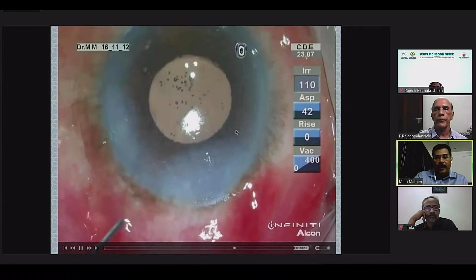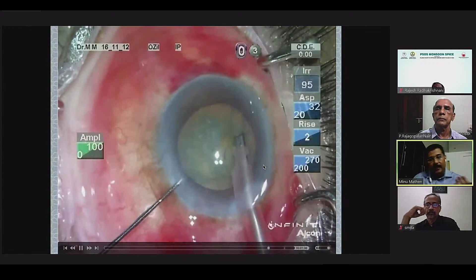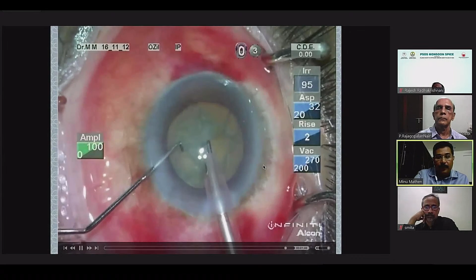And here again, if you notice, there is fluid going between the phaco needle and the sleeve. This prevents the heat being transmitted directly onto the incision. But if we tend to move the probe towards the sides like this, it will obstruct the fluid flow through that, and you can transmit heat energy directly onto the edges and sides when you're doing phaco. If you press down, when you're tilting the tip down, this will pressurize the posterior lip, and also if you lift up, it will pressurize the upper lip. All those can cause phaco burns.